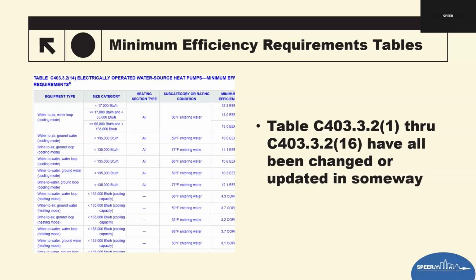So for plan reviewers, when the equipment schedule comes in, you should identify the table that applies to the listed equipment. Verify the rating condition. Is it EER? Is it COP? Is it IPLV? Is it IEER? Make sure those match the required table, and then ensure the unit's listed efficiency meets the minimums. And then watch for mislabeled or outdated AHRI references, common during code transitions. So if your city is going to update to the 2024 and you're on the current 15 or 18 or even 21, make sure that those references are matching.